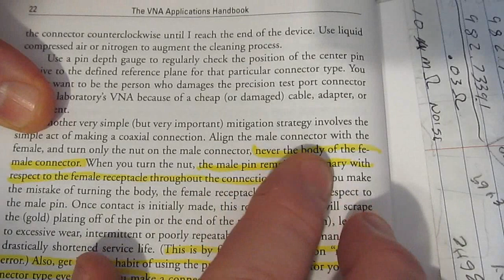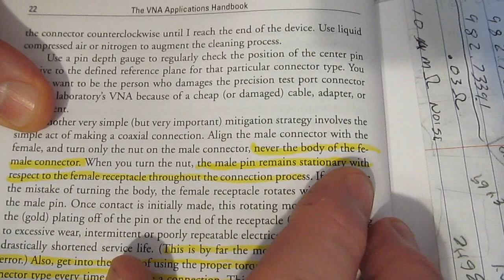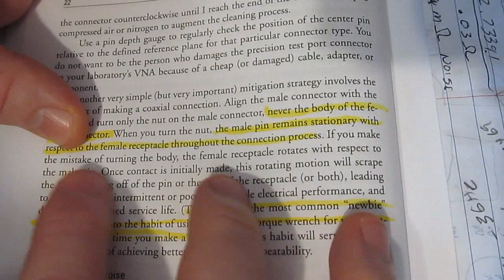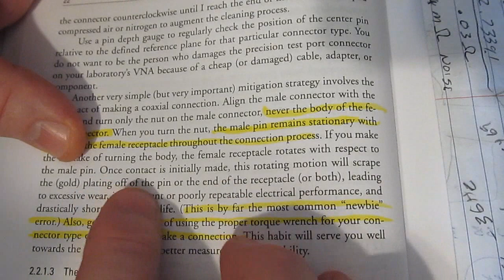Again, I want to refer to our book. This is on page 22. Align the male connector with the female and turn only the nut on the male connector, never the body of the female connector. When you turn the nut, the male pin remains stationary with respect to the female receptacle throughout the connection process. Again, you never want to have that center pin rotating inside of the mating connector. The book goes on to say, if you make the mistake of turning the body, the female receptacle rotates with respect to the male pin.